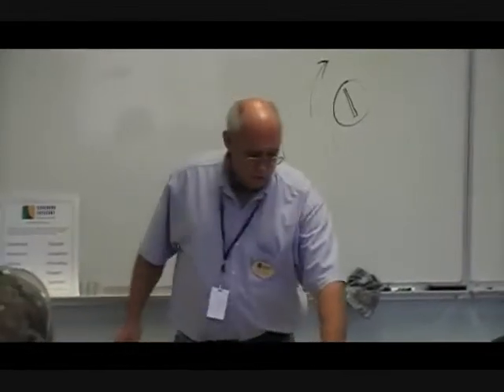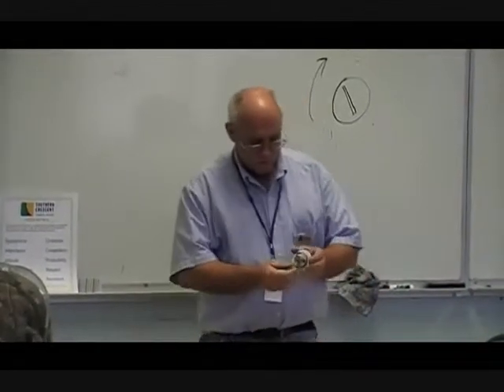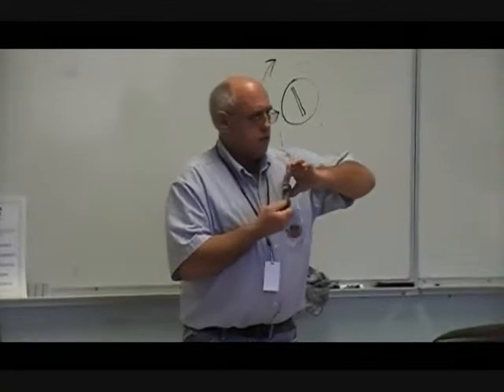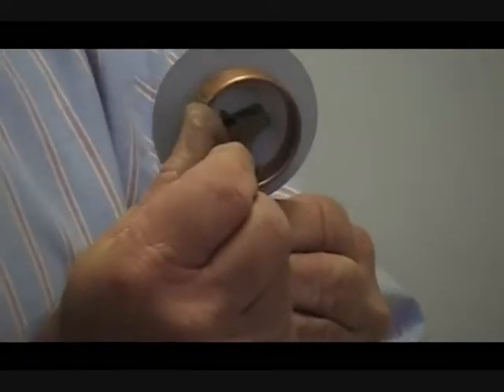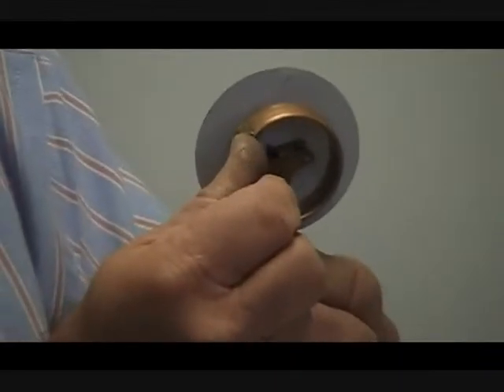Now, the way the gauges work is not a mystery. You see this tube right here? As this pressure increases in here, it causes this tube to try to straighten out. That tube is connected to some gears, and that's what moves the needle. Now, the needle's gone off of here, but I think you can see this a little bit closer. If you just take that and move that, you can see that right there.